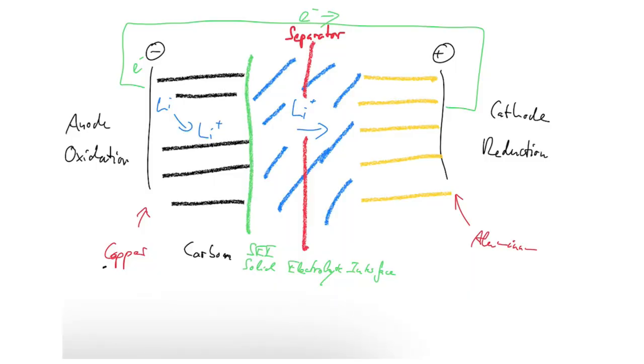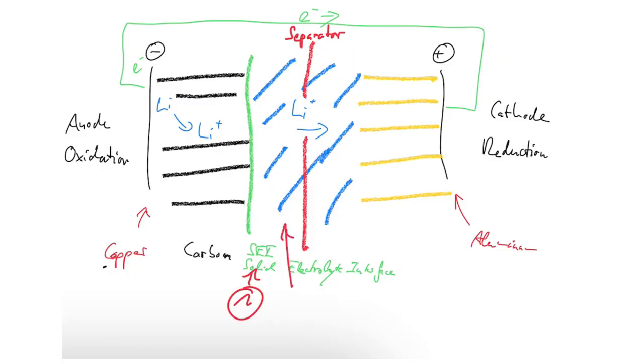At the beginning nothing really is visible — it's all happening inside. First you have external heat, then slowly the solid electrolyte interface (SEI) layer is affected. That's the layer from the anode to the electrolyte and it helps the ions go from the anode into the electrolyte. This SEI is decomposing — at first it's only damaged, but this damage already increases the reaction and the temperature, and then it gets more and more damaged. At one point the electrolyte also becomes part of this reaction. Because the electrolyte is fluid, at a certain temperature it starts boiling, turning into a gas, and with that transition from fluid to gas it expands significantly in volume, leading to a pressure buildup inside the cell.